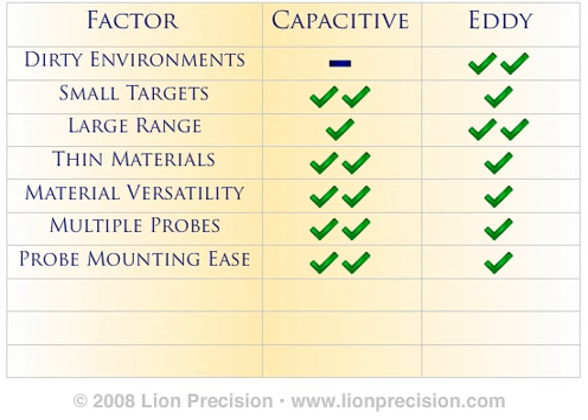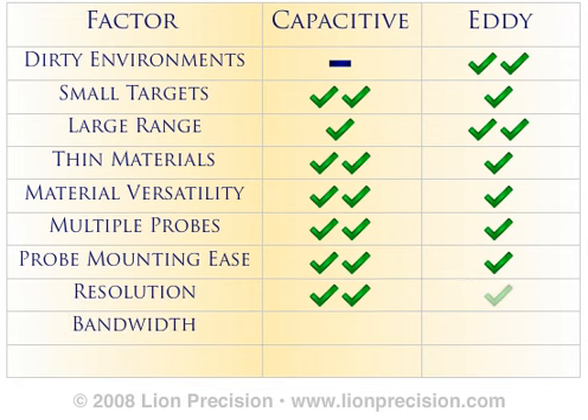Two other specifications differ between the two technologies: resolution and bandwidth. Capacitive sensors have a higher resolution than eddy current sensors, making them a better choice for very high resolution, precise applications. Most capacitive and eddy current sensors have bandwidths between 10 and 15 kilohertz, but some eddy current sensors have bandwidths as high as 80 kilohertz. Another difference between the technologies is cost. Generally speaking, eddy current sensors are lower cost.